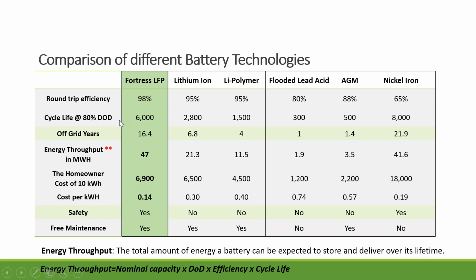We did studies on each battery, letting them discharge at 80%, and that gives the cycles for the different chemistries. For off-grid years, if you do one cycle a day, how long can the battery last? It varies - with LFP you're talking about 16 years, the other ones about 7 years. Flooded lead acid and AGM are much less if you do 80% depth of discharge.